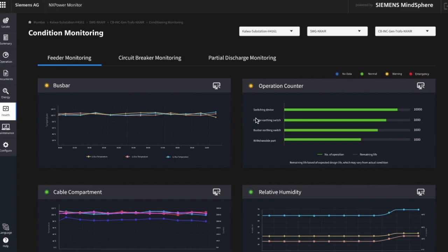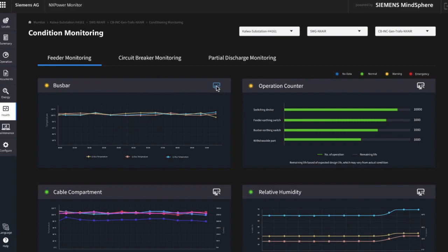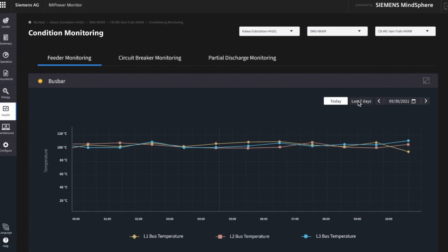To analyze better, you can zoom into the charts by clicking the icon in the top right corner of the line chart, for example the bus bar. There are temperature and humidity sensors within the bus bar and cable compartments for air-insulated switchgears. For gas-insulated switchgears, only the cable termination chart will be shown.